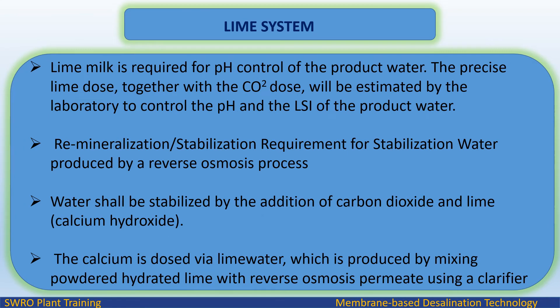The lime system provides lime milk required for pH control of the product water. The precise lime dose, together with the CO2 dose, is estimated by the laboratory to control the pH and the Langelier Saturation Index (LSI) of the product water. For stabilization, water produced by reverse osmosis is stabilized by the addition of carbon dioxide and lime (calcium hydroxide). The calcium is dosed via limewater using a clarifier in reverse osmosis permeate.